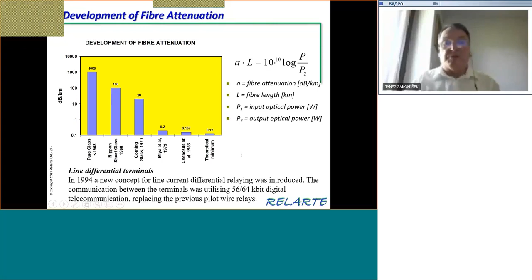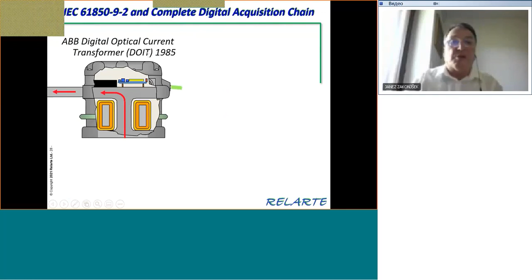We're talking about the complete digital acquisition chain, but here I'll focus on the optical current transformer, called the Digital Optical Instrument Transformer, developed by ABB in 1985. Interestingly, it was used a lot on series capacitors, because it was necessary to have a current transformer on series capacitors at very high voltage, requiring isolators, otherwise it would not be possible to use it.